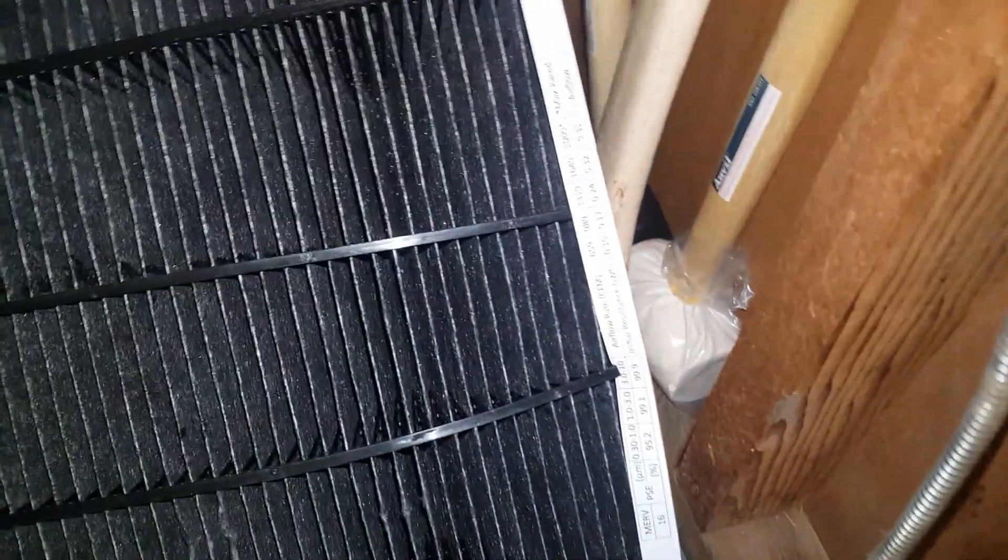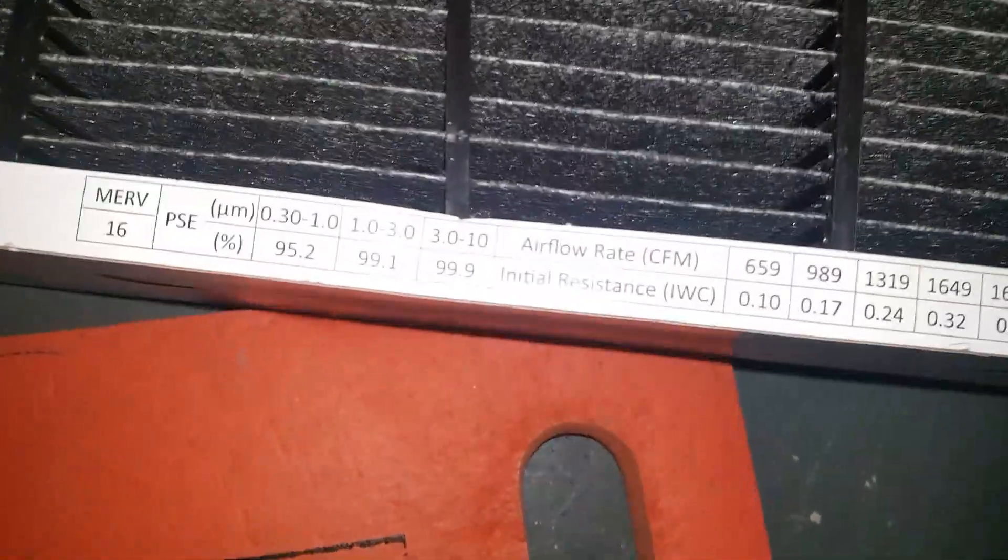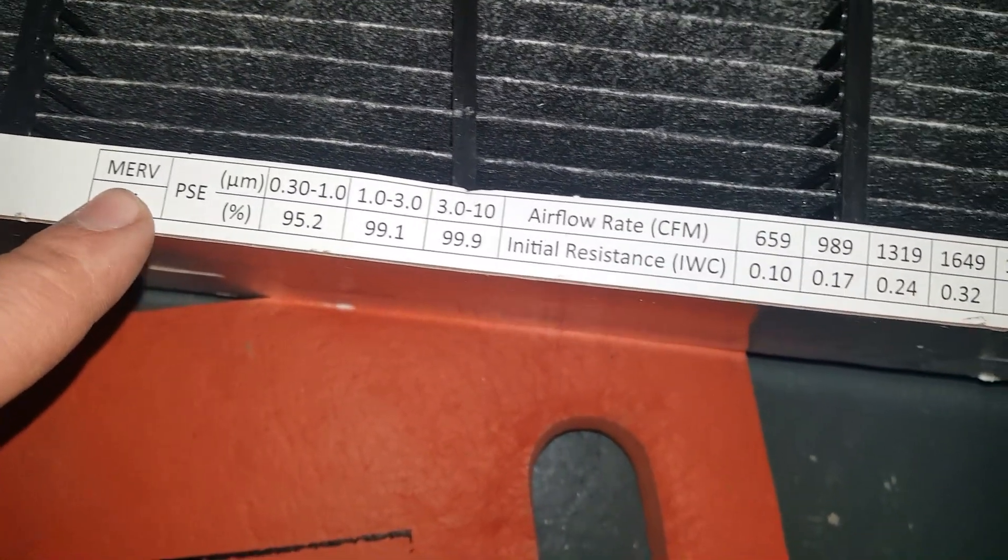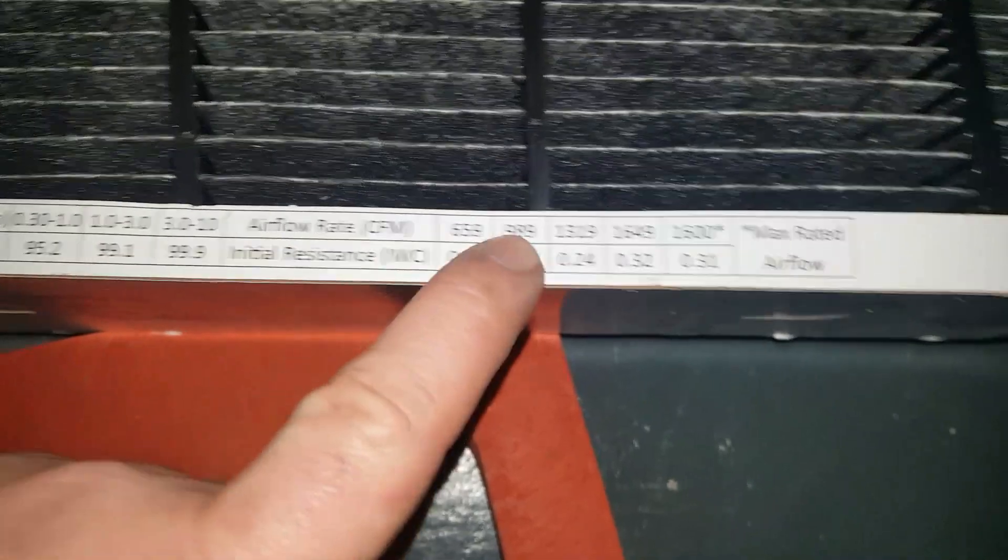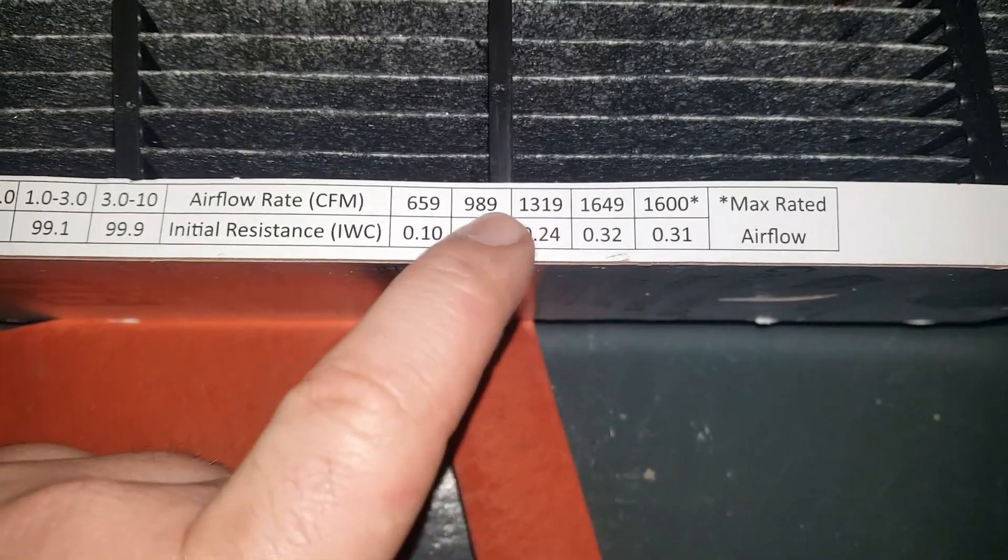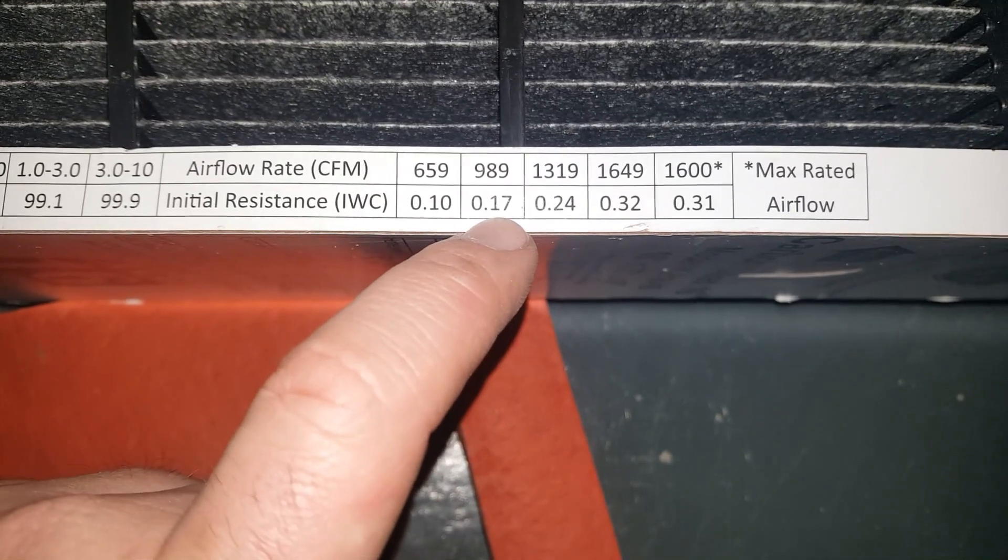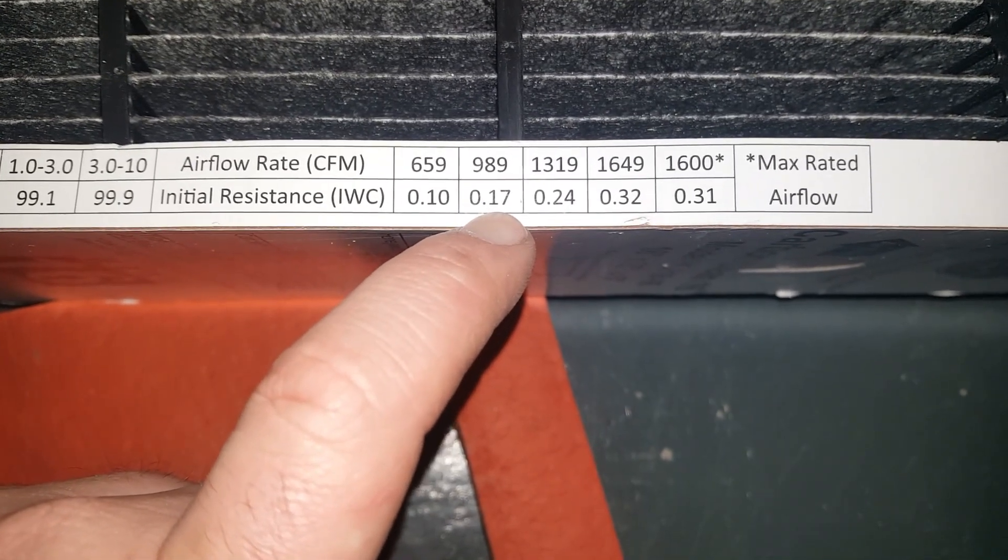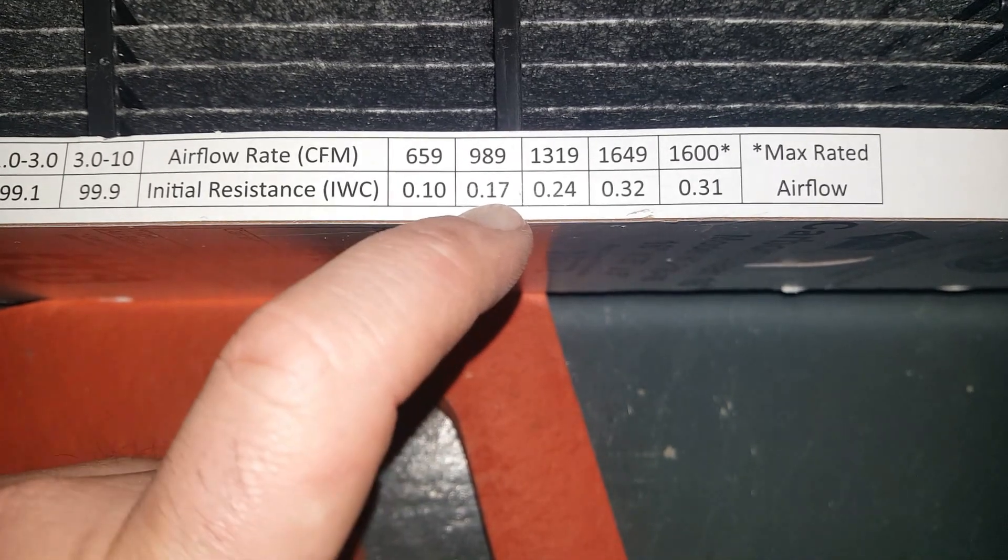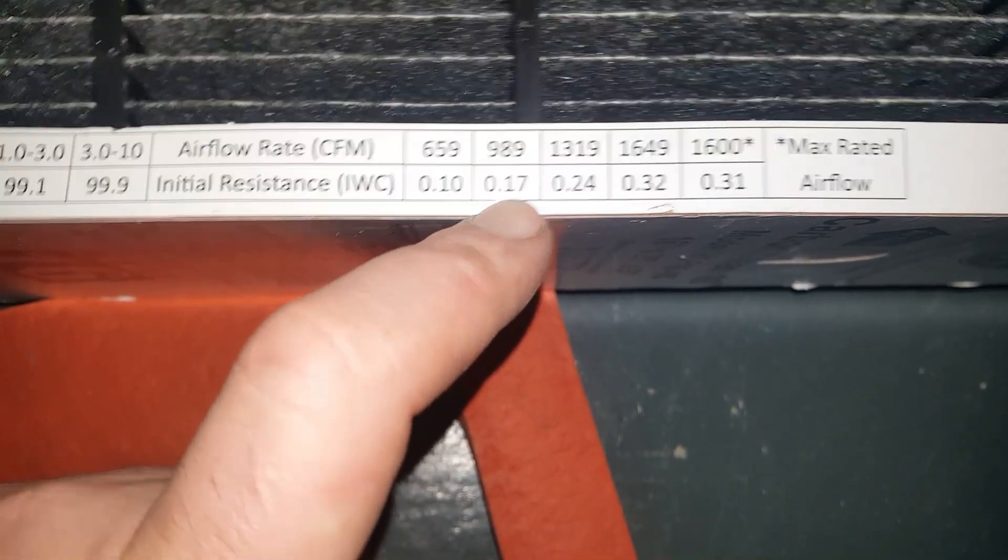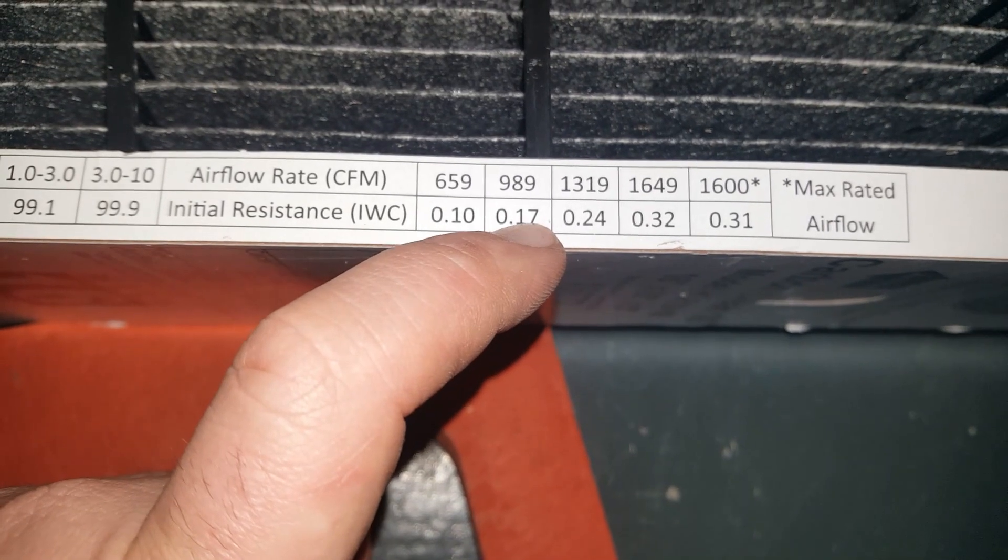Anyways, I wanted to show you guys something here. Not all of them, but some of them will show you the filter drops on these. So this is a Merv 16. Air flow rate, we're right around here, so we should expect a resistance drop of 0.17 or around there. So let's put this in and see what we got.